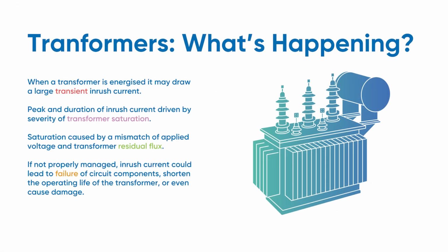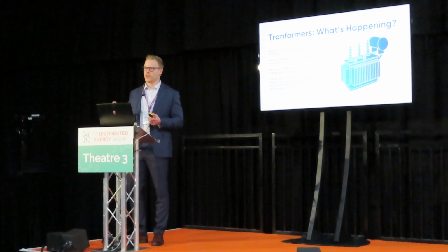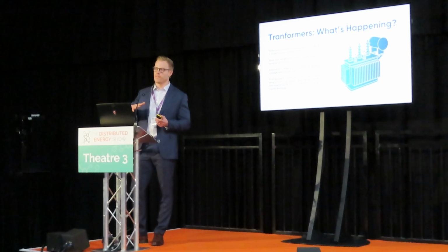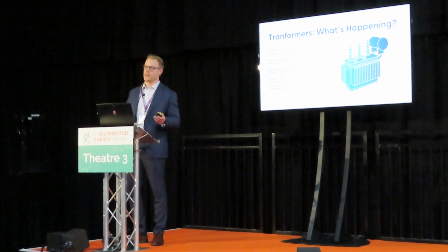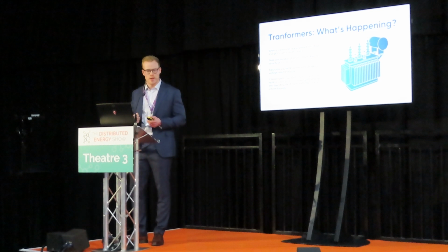Now, why is this important? How can this be utilized? One of the common problems we have is energizing transformers on these weak networks. A transformer is used to take a voltage from one level to another level. When the transformer is energized and there's not much load on it, it's not really doing much. It's a steady state. The issue we have with transformers is when they're off and we want to turn them on for the first time, or if they've tripped, for example.